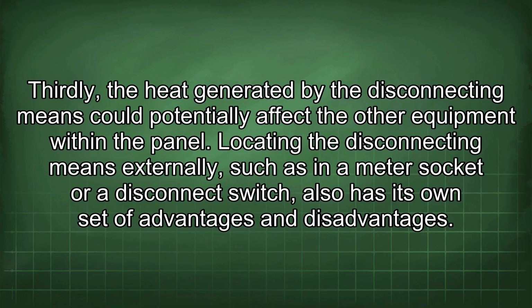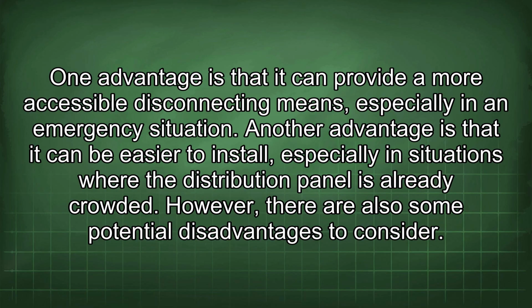Locating the disconnecting means externally, such as a meter socket or a disconnect switch, also has its own set of advantages and disadvantages. One advantage is that it can provide a more accessible disconnecting means, especially in an emergency situation. Another advantage is that it can be easier to install, especially in situations where the distribution panel is already crowded. However, there are also some potential disadvantages to consider.